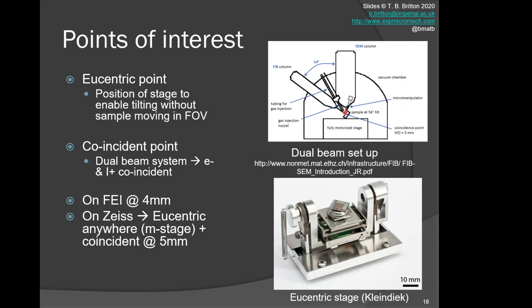In some instruments, Zeiss's instruments for instance, you can select where you would like the eucentric point. There's a secondary stage that means you can move the sample around and change that eucentric, and you can divorce the eucentric from the coincidence. With Thermo Fisher or FEI instruments, they're often fixed at the coincident point, and the eucentric points are actually the same location in the microscope. Just to note that the angle between the FIB column and the SEM column can change—they're often 52 or 54 degrees depending on the particular instrument you're working with. If in doubt, ask the people who are training you. Do not assume it's the same between manufacturers, and check on the columns you're working on.